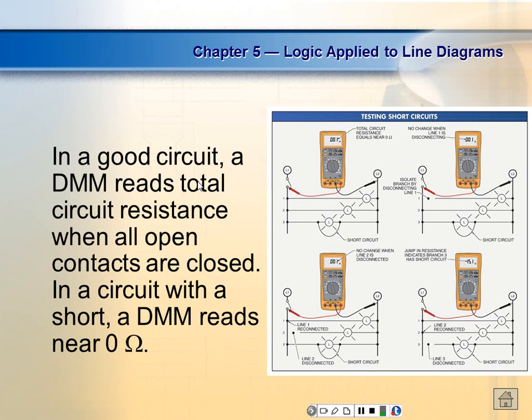Well, I have a question about the procedure we use at USDA. We have like 8 or 10 motors on a roll line running through one cabinet, and to check if one of them is shorted out or bad, to figure out which cabinet it's in, you put the black lead to the cabinet and the red lead to the fuses after you turn the power off. They're supposed to read OL, but if one of the fuses comes up with numbers, then one of the motors in there is shorted. Could be, or has low resistance, yeah. That's how we do it.